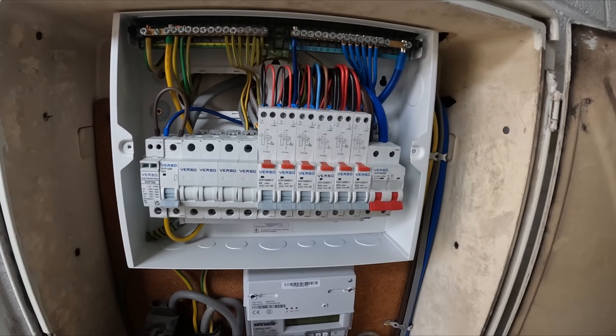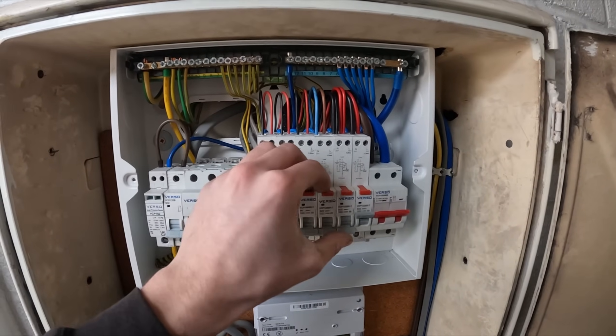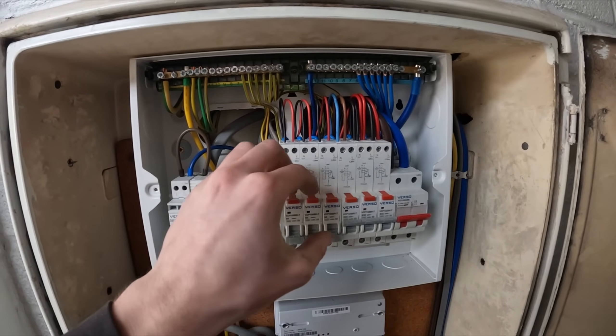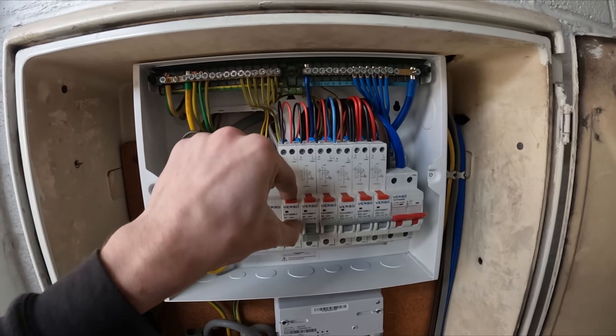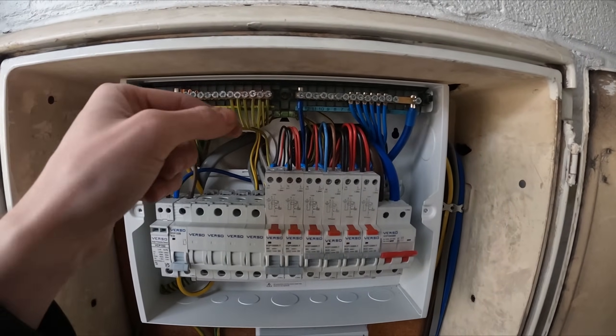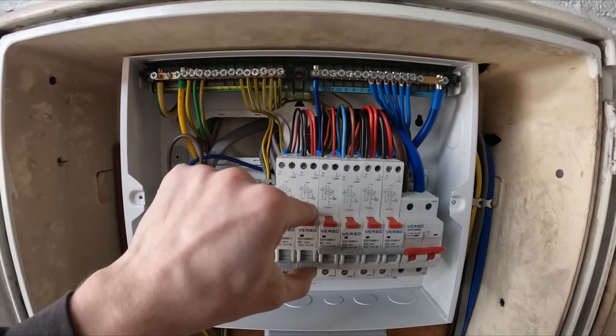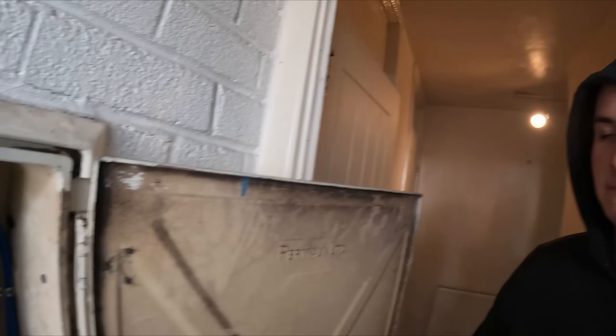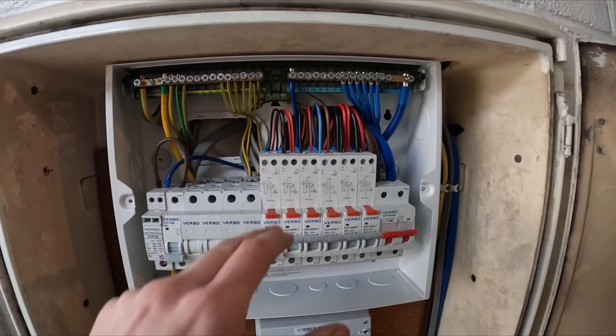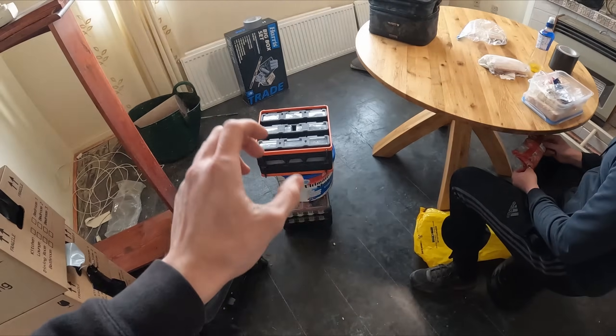Right Ted, moment of truth — main switch on, busbars all torqued up. Cooker's fine, ring main's fine. Normally it's the lighting that's an issue — that socket's fine, that one's fine. But there's a lighting circuit that won't come on. About 30 seconds later — turns out it was a shared neutral. I piggybacked them across and, moment of truth, there we are — lights are on, job's good. A quick easy fix; I thought we were going to have hours of testing a fault.